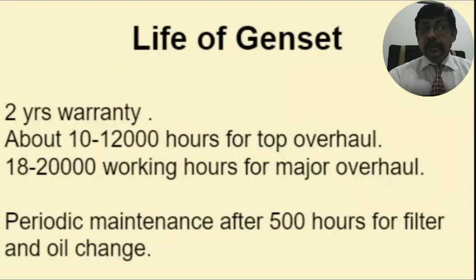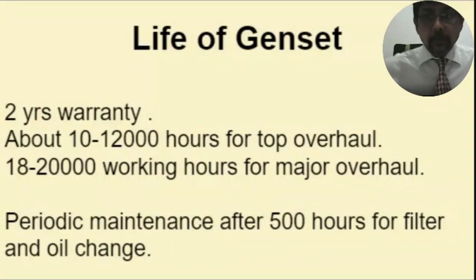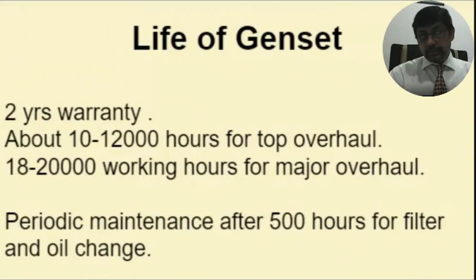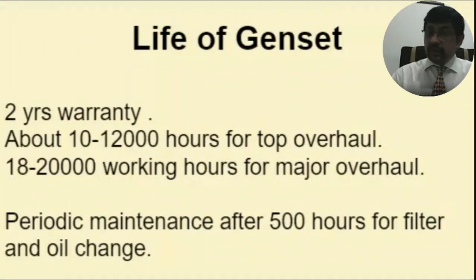Next, the life of the genset. The life of the genset is about 10 to 15 years, because we assume running it at about 1500 to 1800 hours in a year, which makes it about 20,000 working hours. The warranty of the generator is 2 years, first of all. So for the 2 years, if anything happens, the company will give you service free of charge.